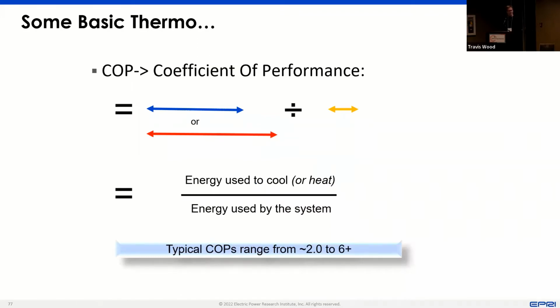What you want to pay attention to is the relative lengths of those lines. These lines represent the amount of energy contained in the process of evaporation, condensation, or compression. The longer the red line is—and red represents heat being rejected into a space—in a heat pump, red would be the good heat you're putting into the space. The ratio of the red line to the yellow line, which is the energy you're putting into the compression process, determines how efficient this is. With a gas furnace, you burn a unit of methane, and at most you can get that much heat into the space—at most 100% efficiency.